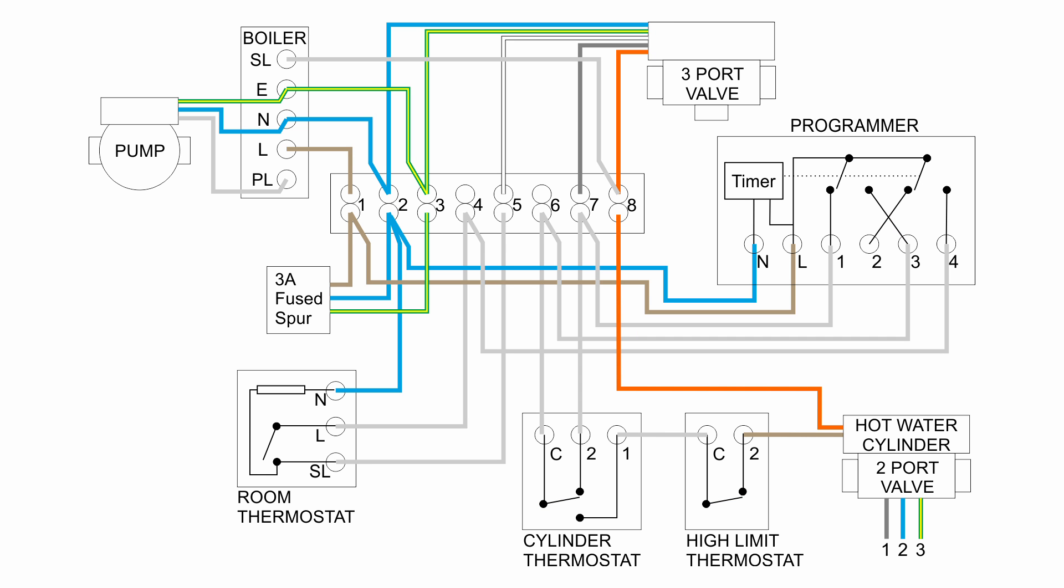Now the two items which are added with an unvented cylinder are the two-port valve which we've seen previously, so that's obviously what cuts off the water supply in the case of some kind of problem, and there's also a second thermostat which we've got shown here at the bottom as a high limit thermostat. And this is a thermostat which, when the temperature of the water reaches a certain point, this will open and cut off the supply of power to the valve.